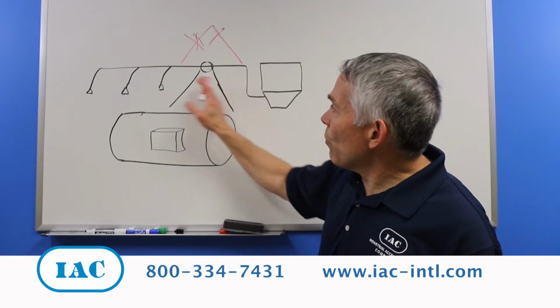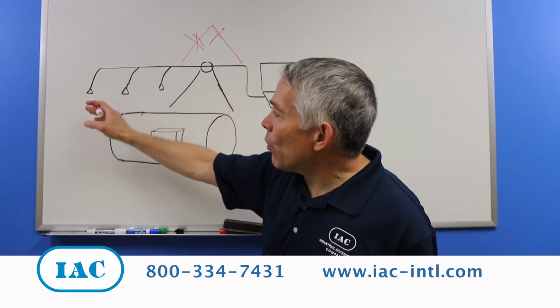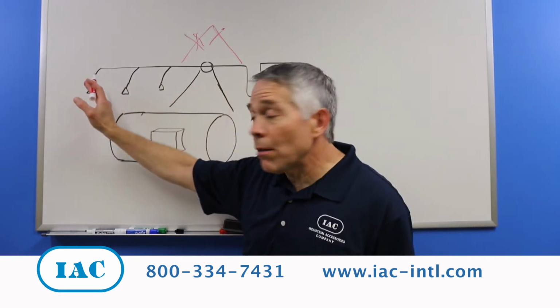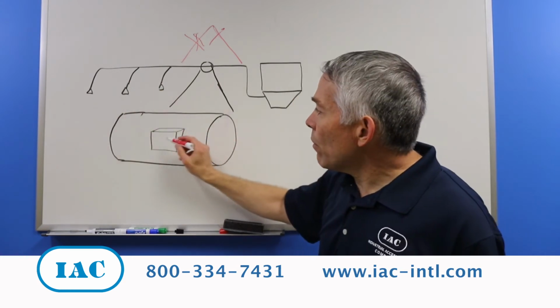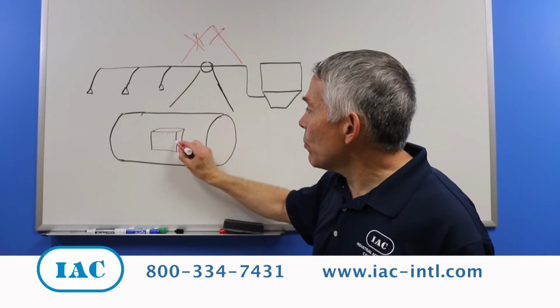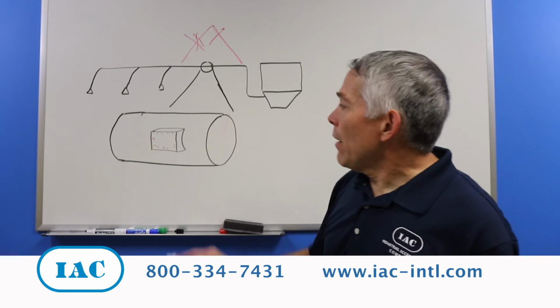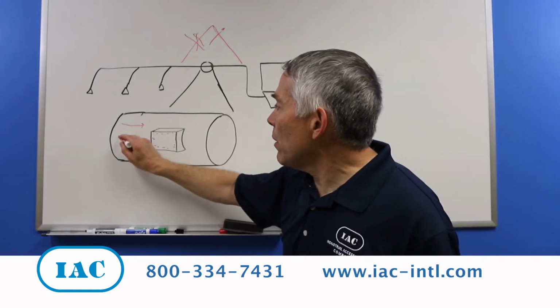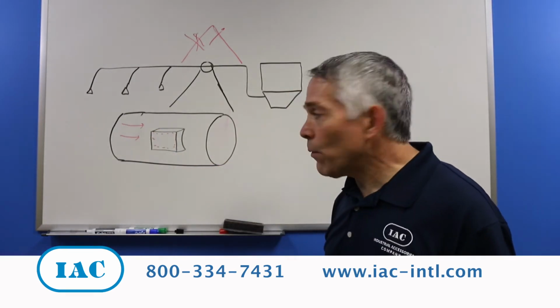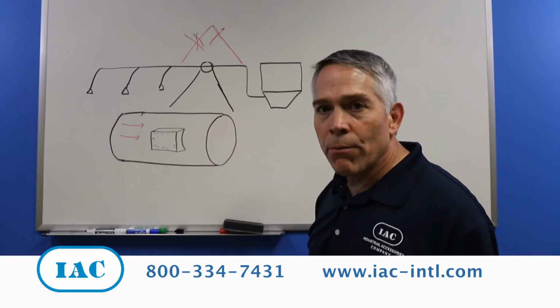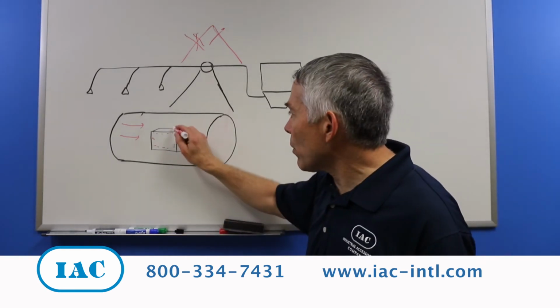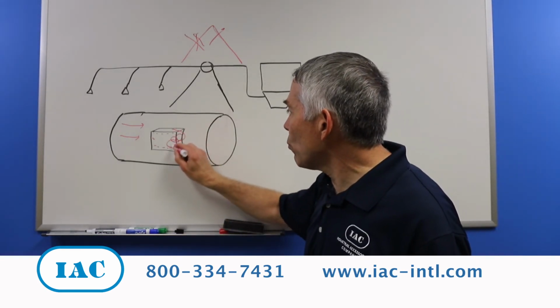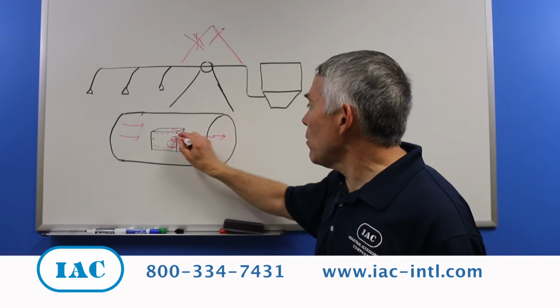So what I have drawn here is horizontal ductwork going to different places to vent in the plant, and these are typical inspection doors. Now think about it: airflow is moving at a high velocity here, around 4,000 feet per minute, and then we have this notch protruding out of a round ductwork. Well, that obviously creates turbulence, and then continues.